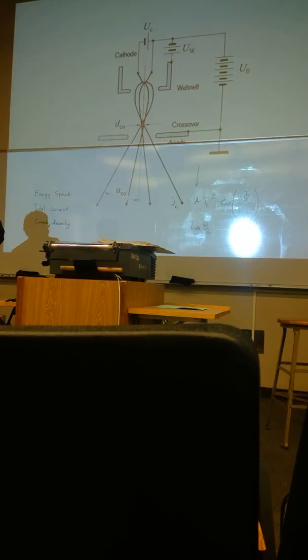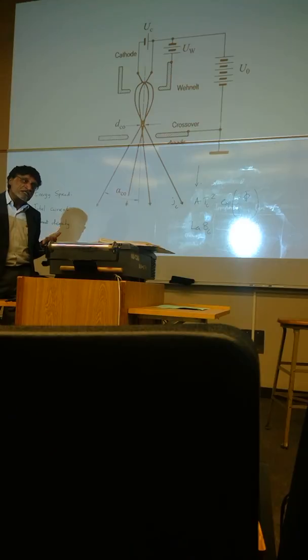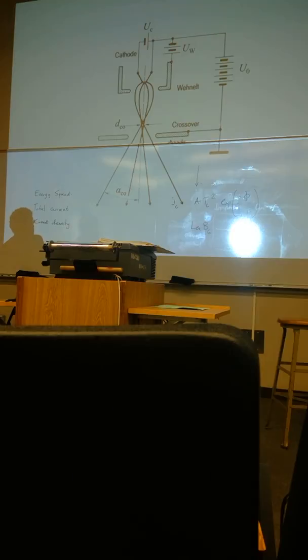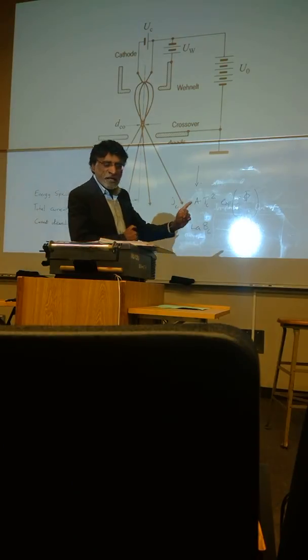Because this is the electron gun, you would have the magnetic coils after it. There would be a number of coils. There's one set of coils called the condenser lenses, then the objective lenses, then the projective lenses, and so on. The main imaging workhorse, like in any other microscope, is the objective lens. We'll talk about microscopy in a little bit, and about optical microscopes after this chapter, where essentially you do the same thing. All right, so that's the gun. Any questions on this?